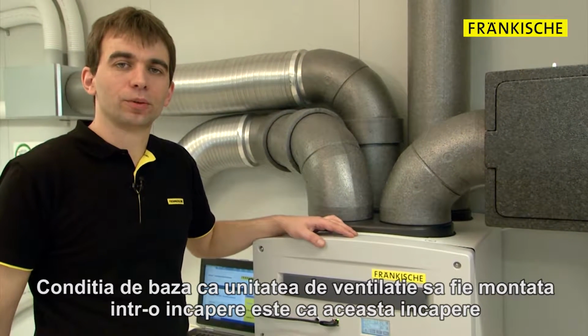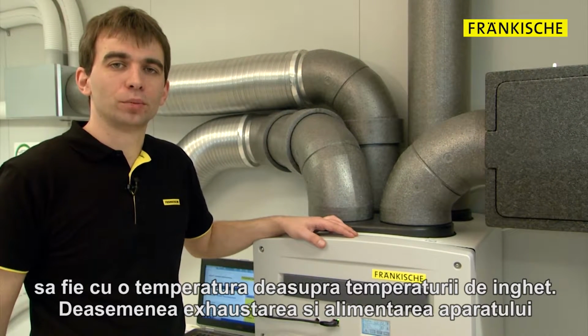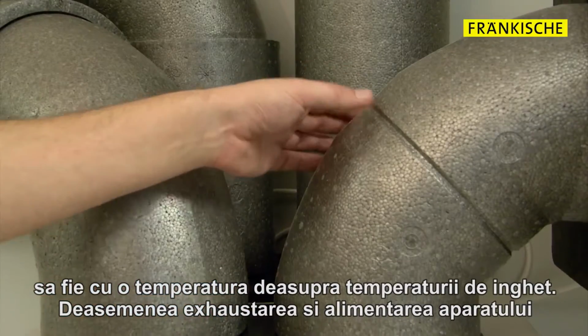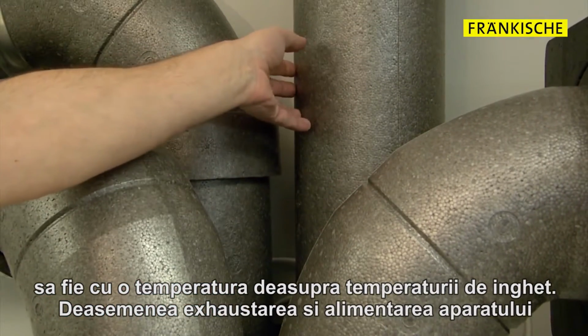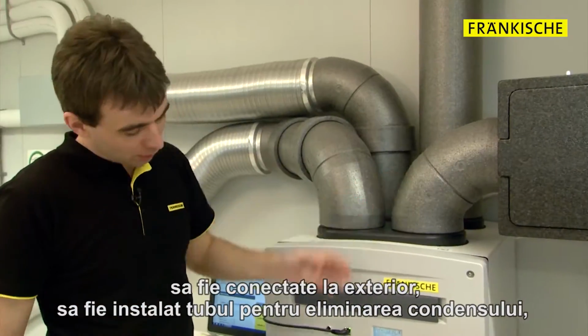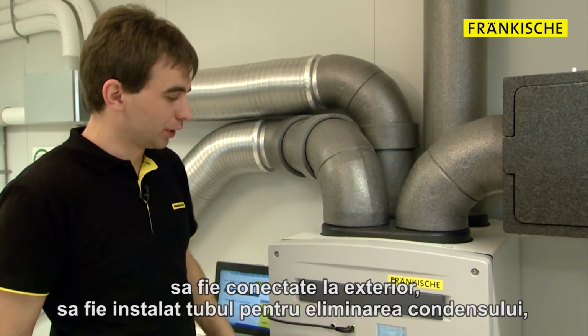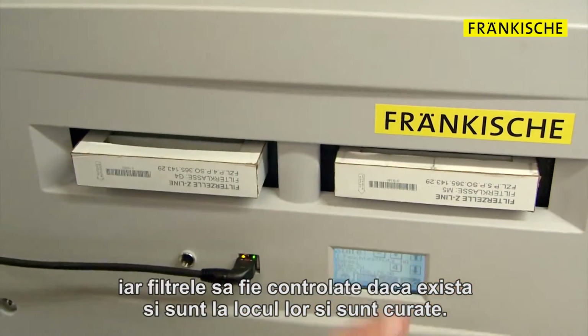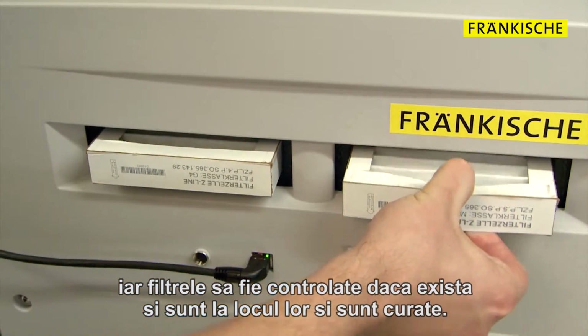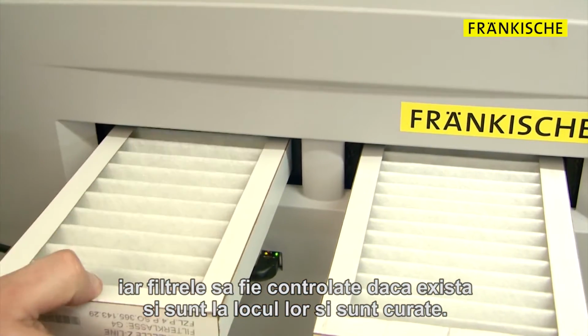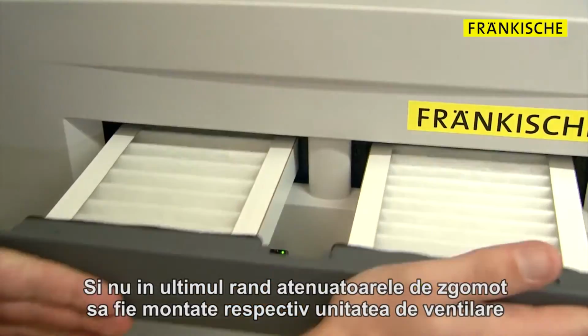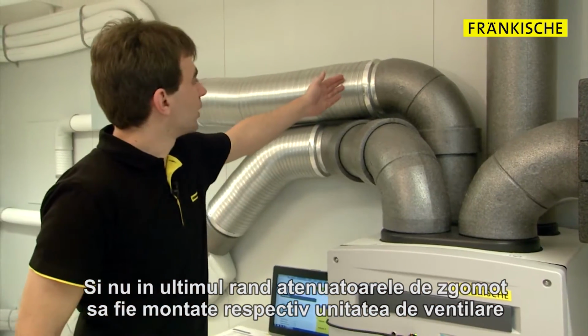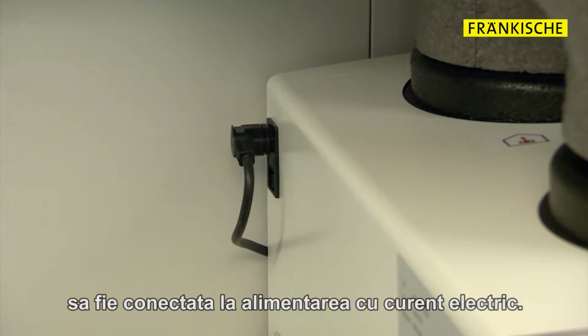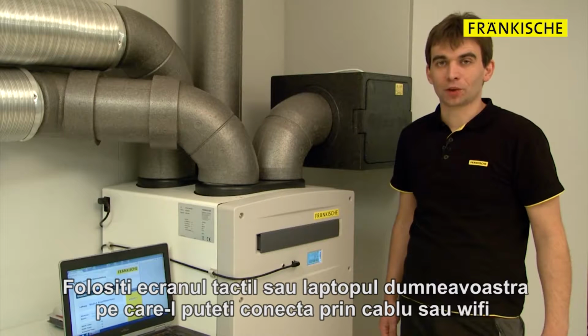Technical preconditions include the installation of the ventilation unit in a frost-free place, that the insulated incoming and exhaust air conduits have been connected, that the installation of the condensation drain has been completed, that the filters have been inspected for cleanliness, that the silencers have been installed and the power supply has been connected.